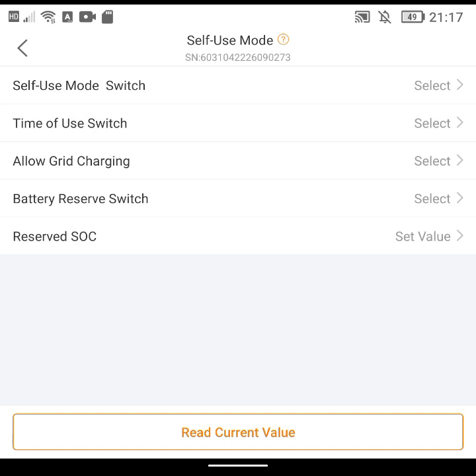I've also played around with the Set Reserve and the SOC here. This is when I was playing around with the battery settings and managed to get it to charge in the middle of the day from about 10% up to 100%. It was a cloudy day so it didn't actually cost me anything extra, but at least from that I've worked out that it's going to take about an hour and a half to charge my battery from 10 to 100%.